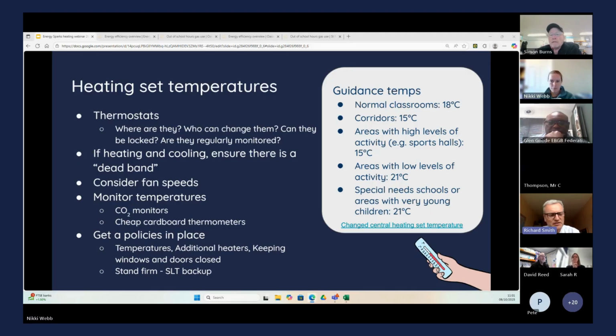It's also worth mentioning that in older schools, some thermostats with a convection heater or blow fan radiator are actually controlling the electric fan, not the heating itself, since that's just on the heating circuit. I've got thermal camera pictures showing the hot pipe still trickling heat in when the fan's off, but once the thermostat calls for more warmth, it kicks on the fan, blowing air across the hot pipes to get warm air into the room quickly. These can be very reactive and good for big spaces, but in classrooms the feedback is always that they're too noisy, so people just leave them off and let the heat trickle in, which is no bad thing really.